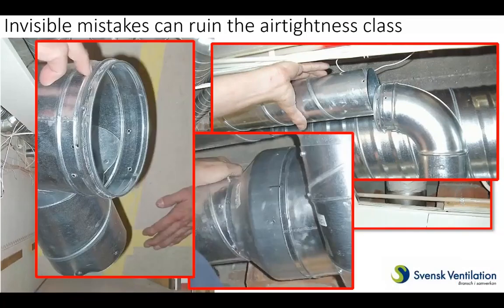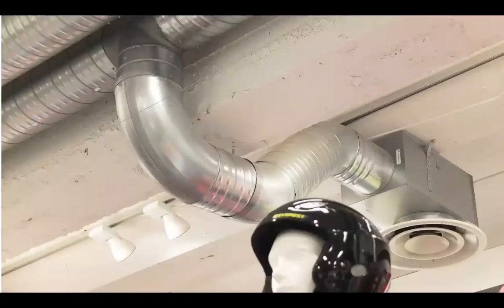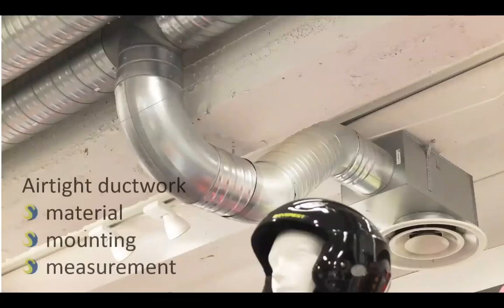And here are some other cases of the same kind, where extra invisible holes from screws that were taken out ruin the airtightness class. So my warning for that. And that's actually the end of my presentation, almost.